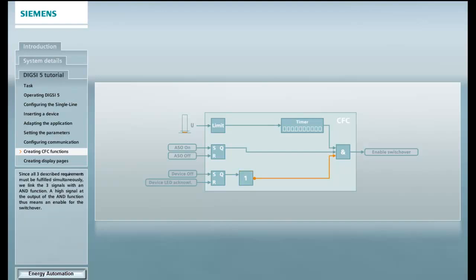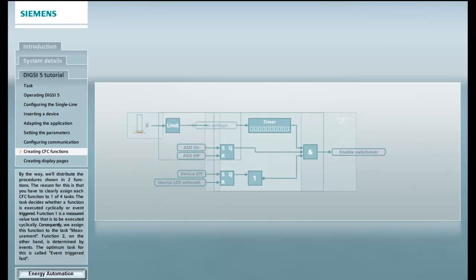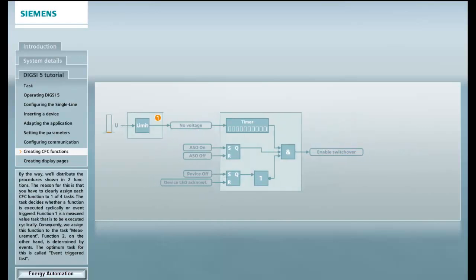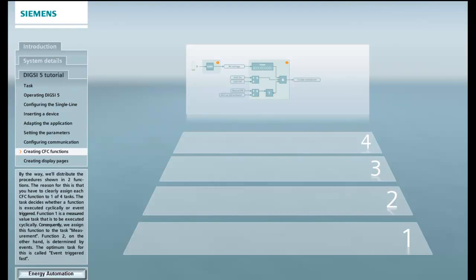Since all three described requirements must be fulfilled simultaneously, we link the three signals with an AND function. A high signal at the output of the AND function thus means an enable for the switchover. By the way, we'll distribute the procedures shown in two functions. The reason for this is that you have to clearly assign each CFC function to one of four tasks. The task decides whether a function is executed cyclically or event-triggered.